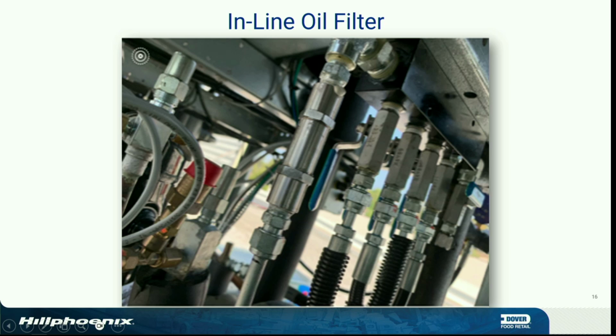So we also have one coming off our reservoir to our header manifold for our compressors. The reason we started doing this was because back in 2016, 2018, we were seeing a lot of trash getting in our separator solenoids, the oil compressor solenoids, and stopping them up, either stopping them from working or keeping them open all the time. And a solenoid or a compressor stuck open is not a good deal. Because what's going to happen next? You're going to flood that compressor out. And guess what happens when it starts? Boom. You get a halo of oil out that discharge 2050 relief valve, and it goes everywhere.